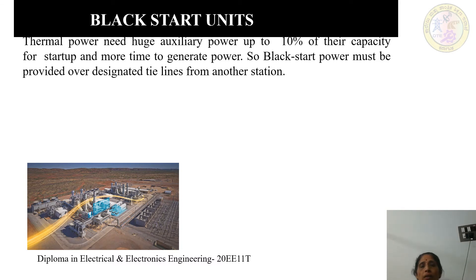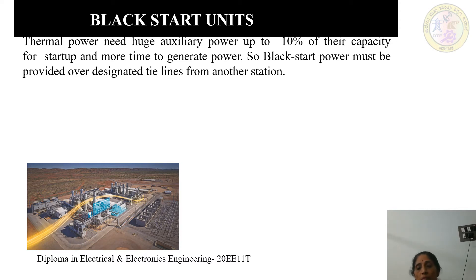So, what are blackstart units? Thermal power plants need huge auxiliary power — up to 10% of their capacity — for start-up, and they need more time to generate power. Normally thermal power plants take 6 to 8 hours to start. Therefore, blackstart power must be provided over the designated tie lines from another station.